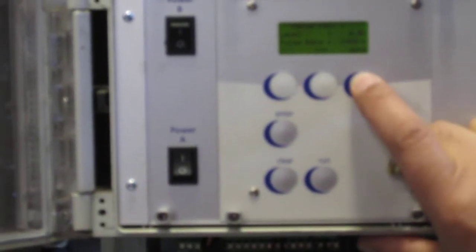So now we're at value pair 1, which is 0%. Right now we have the source closed, so that'd be full. We're mimicking a full. So you can make 100% there, or you can make it 0. Doesn't matter which way you go. But we'll go on and do the 100%. So with the thing closed, it mimics it as full. That's right. It's simulating it full because you're blocking the radiation.